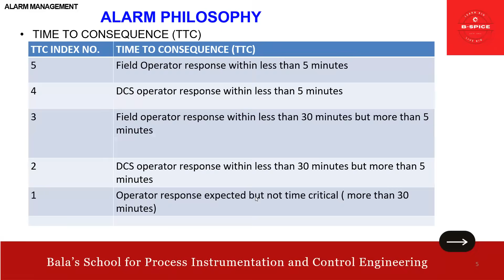Just remember this. Then here operator response is expected, but not time critical, right? So it can generally not be expected from the DCS or field operator to immediately solve a motor or valve failure. In most cases, they have to engage a maintenance team. In general, the DCS operator's risk of forgetting or ignoring the alarm is relatively low, as failing motors and valves will usually hinder his ability to continue the operation in a proper manner. So what he will do, he will just inform the maintenance team. So mostly not time critical.